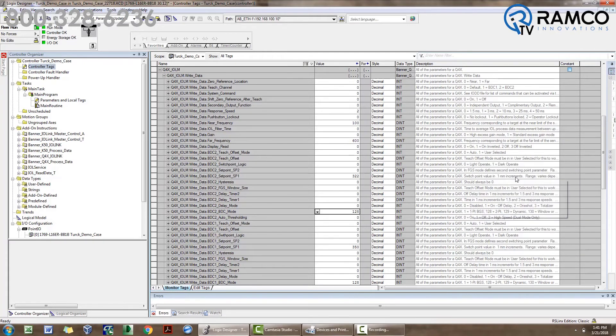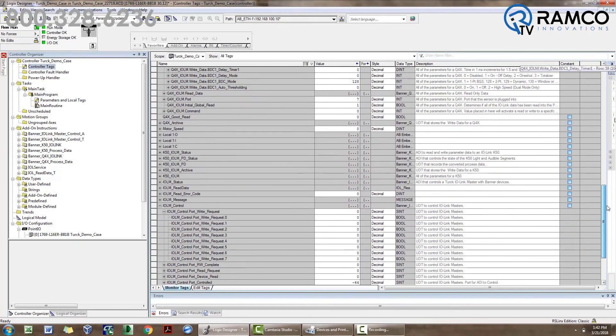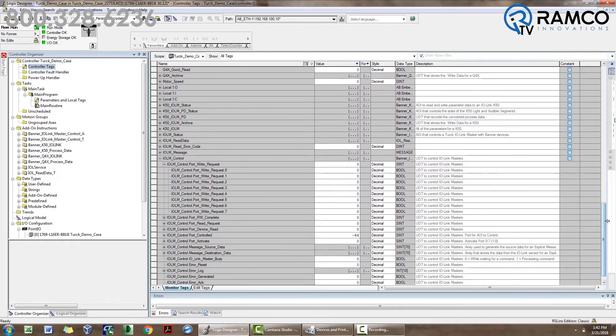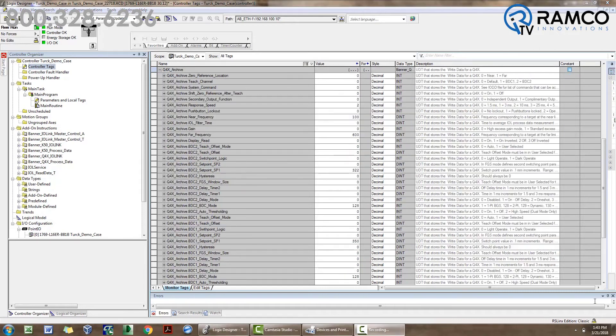Just follow the descriptions for each tag. To save these values to the sensor, go to the IO-Link master control tag and enter a 1 in the port the Q4X is connected to. Remember, this is bit level, so with my sensor connected to port 7, I will turn on bit 6. To verify that the sensor accepted the values, go to the Q4X archive data structure to verify the values changed.